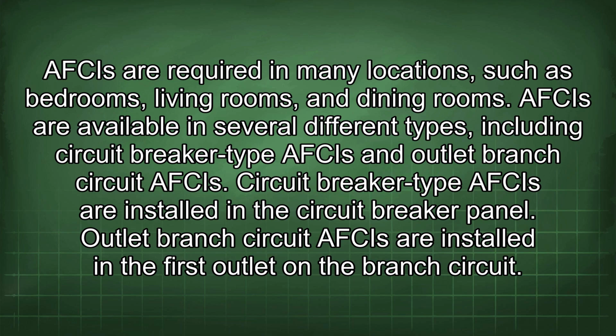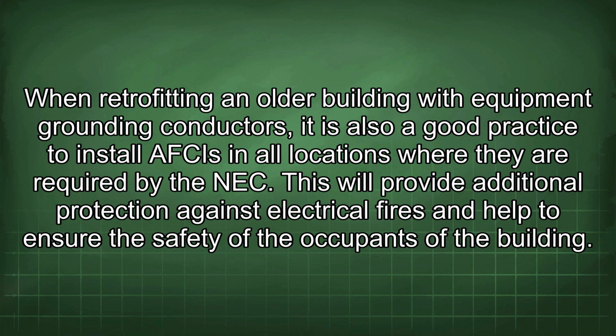Circuit breaker type AFCIs are installed in the circuit breaker panel. Outlet branch circuit AFCIs are installed in the first outlet in the branch circuit. When retrofitting an older building with equipment grounding conductors, it is also good practice to install AFCIs in all locations where they are required by the NEC. This will provide additional protection against electrical fires and help to ensure the safety of the occupants of the building.